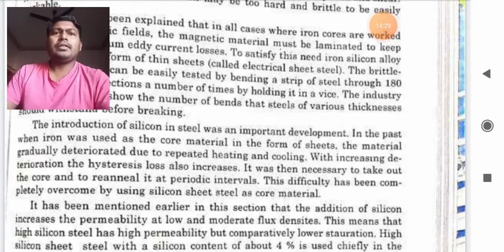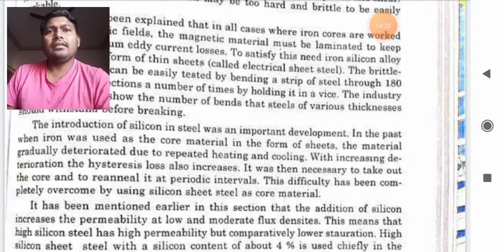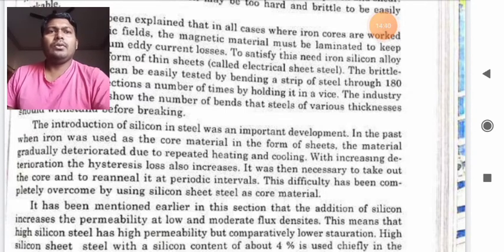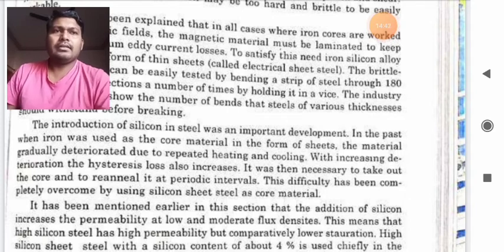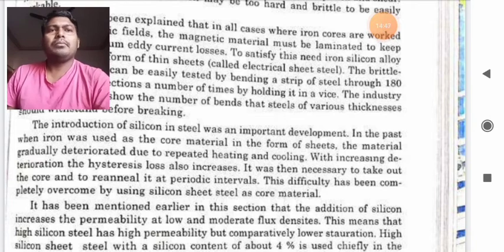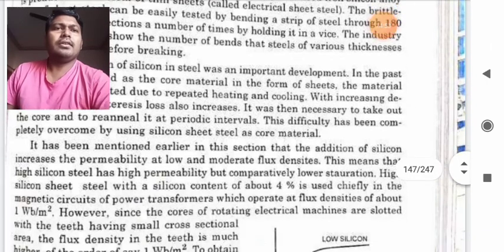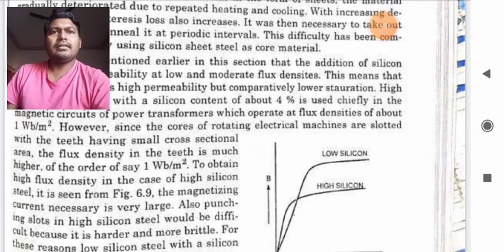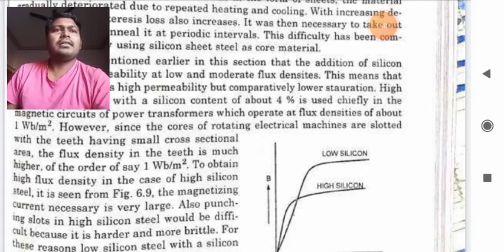It has been mentioned that in the section that the addition of silicon increases permeability. By adding silicon, the permeability of the material is increased at low and moderate flux densities. This means that high silicon steel has high permeability but comparatively lower saturation. High silicon steel with a silicon content of about 4% is used chiefly in the magnetic circuits of power transformers which operate at a flux density of about 1 Weber per meter square.